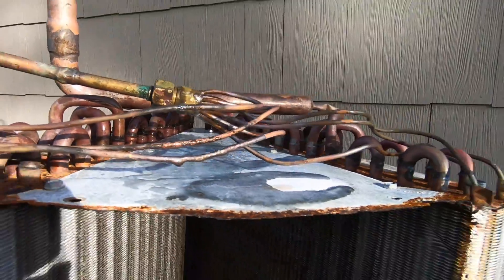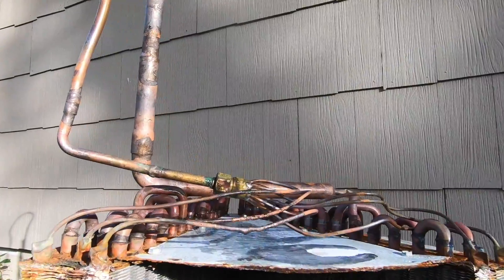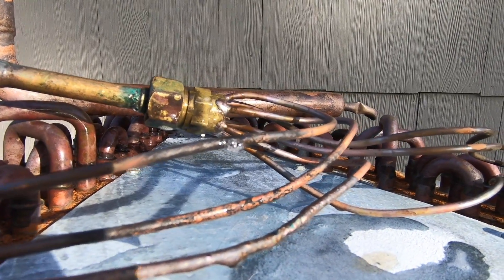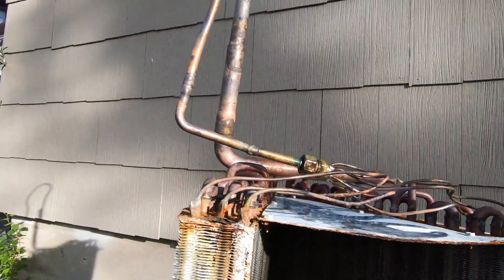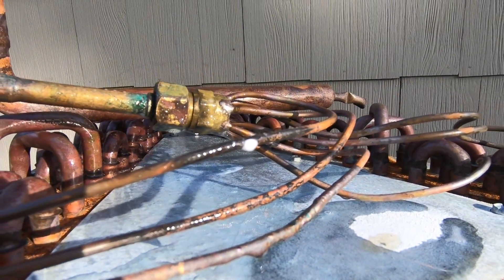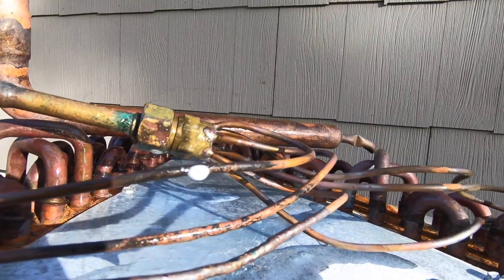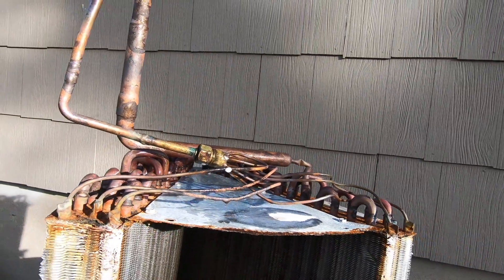So they all work. You've got to decide — I'm not going to say there's a winner or a loser — but in a pinch, a little Windex works. I've actually found some micro leaks with Windex that I couldn't find using some of the other stuff. That's the only reason why I added it into the mix. Till next time, I hope you enjoyed this video.